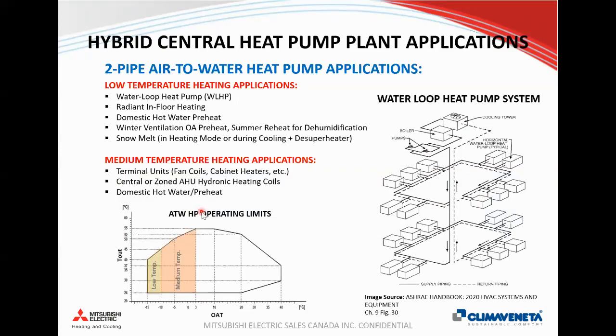So just to summarize briefly about different applications, if we want to use these air to water heat pumps for low temperature applications, water loop heat pumps is a really good application that's shown here on the right. So these are common in condos in Toronto where we have compressorized units inside. So this is one way that we can provide 4-pipe comfort, still with 2 pipes distribution, and individual suites can be in heating mode or cooling mode.